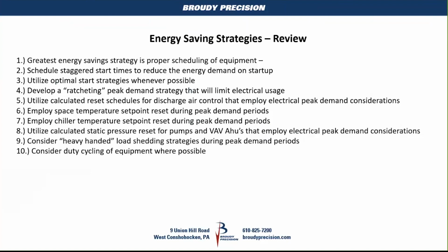That will save them the most money, believe it or not. In the 70s and even today, there are a lot of buildings that just run stuff 24/7. If you turn that stuff off for 12 hours a day, you're reducing the amount of energy they use by 50%. You don't have to be a mathematician to figure out that there's a return on investment that can be realized just by doing proper scheduling.